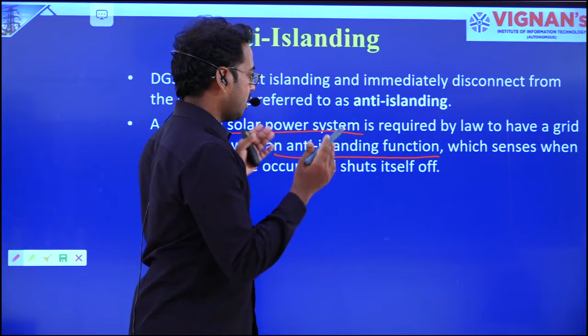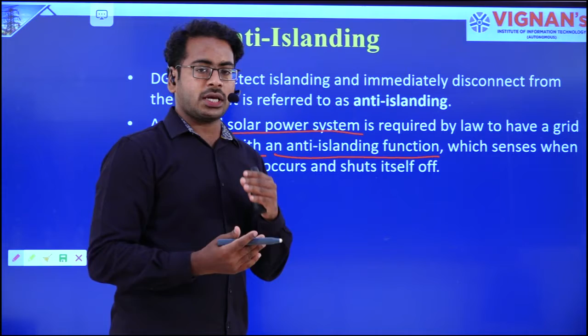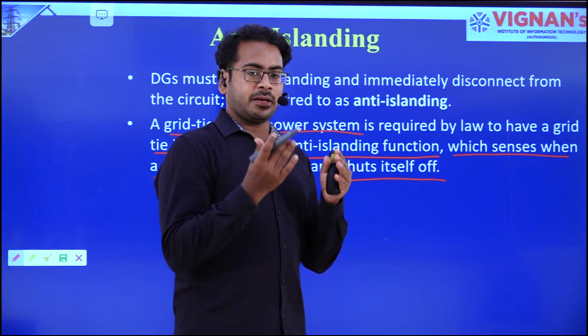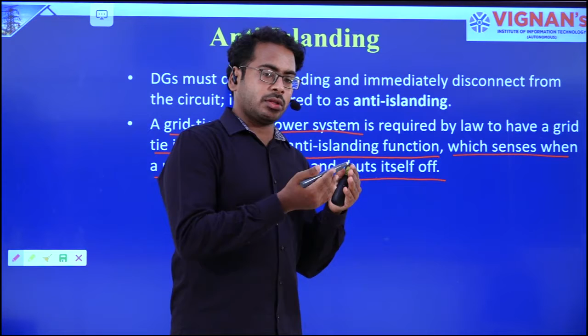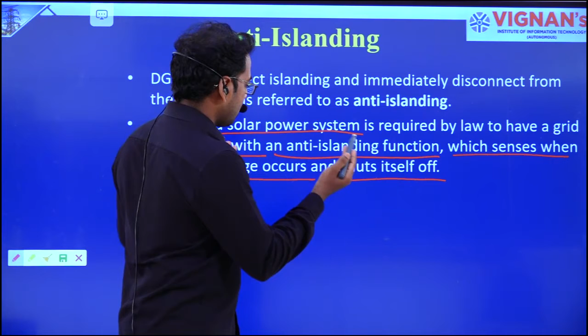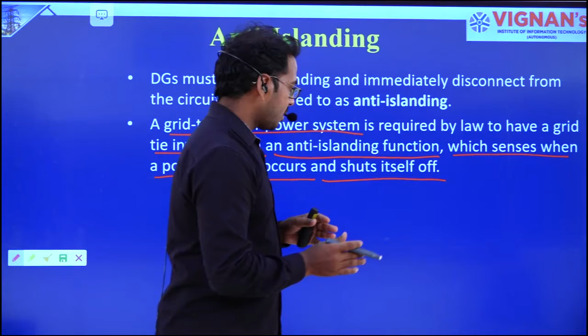So here, a grid-tied solar power system is required by law to have a grid-tie inverter with an anti-islanding function. So the grid-tied PV system must have an inverter with an anti-islanding function, which senses when a power outage occurs and shuts itself off. That means when the grid fails, or the section goes into the islanding condition, a power outage occurs and we will not get any power from the grid side. At that time, the grid-tied PV system inverter must have the anti-islanding function, and it senses when the power outage occurs and shuts itself off. That means the PV system closes, it will not give power to the grid, and it will not operate also.